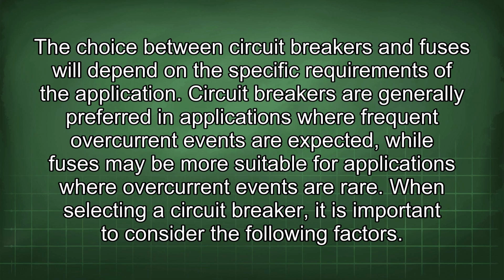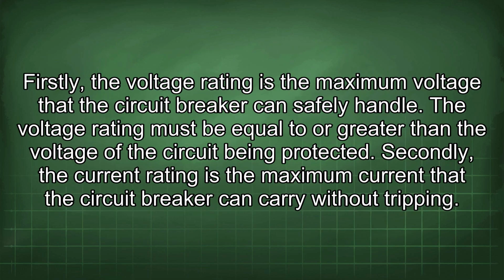Circuit breakers are generally preferred in applications where frequent overcurrent events are expected, while fuses may be more suitable for applications where overcurrent events are rare. When selecting a circuit breaker, it is important to consider the following factors. Firstly, the voltage rating is the maximum voltage that the circuit breaker can safely handle. The voltage rating must be equal to or greater than the voltage of the circuit being protected.